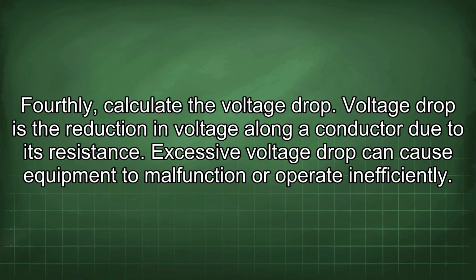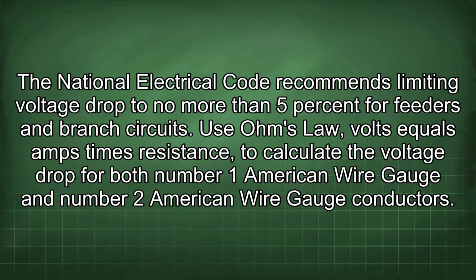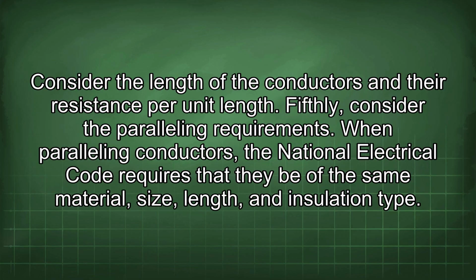Fourthly, calculate the voltage drop. Voltage drop is the reduction in voltage along a conductor due to its resistance. Excessive voltage drop can cause equipment to malfunction or operate inefficiently. The National Electrical Code recommends limiting voltage drop to no more than 5% for feeders and branch circuits. Use Ohm's law, volts equals amps times resistance, to calculate the voltage drop for both number 1 American wire gauge and number 2 American wire gauge conductors. Consider the length of the conductors and their resistance per unit length.